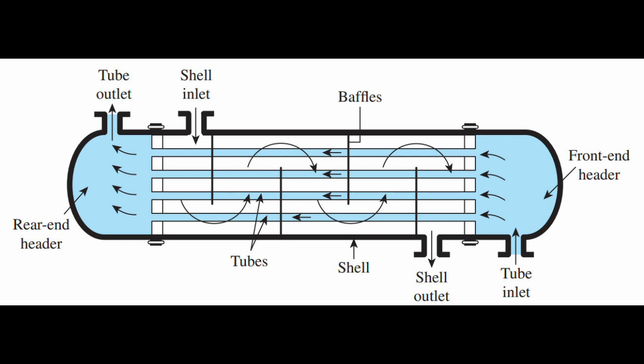This type of cooler uses a series of tubes and a shell to transfer heat from the refrigerant to a secondary fluid, such as water. The refrigerant flows through the tubes, while the secondary fluid flows through the shell. In a shell and tube type evaporator, water and refrigerant enter the cooler from opposite inlets to maximize the heat exchange process.